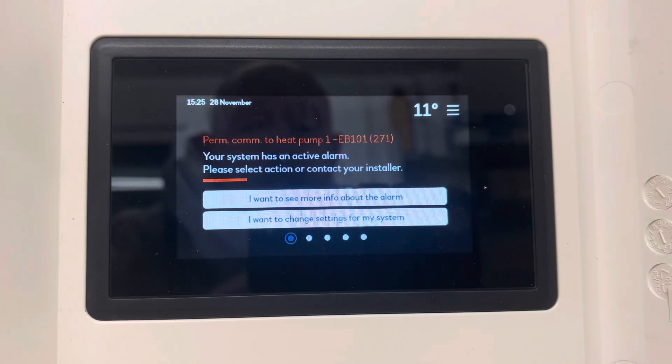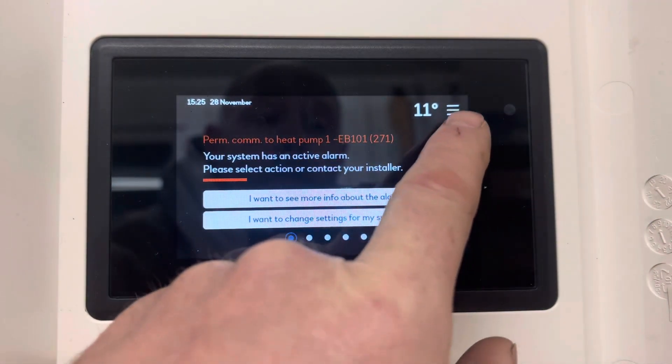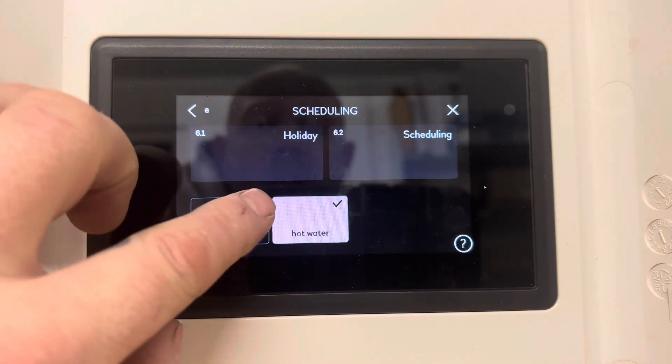We're going to have a look at setting holiday schedules now on our NIBE SMO S40 control. Ignore this error here — this is just a dummy control. So we need to press the button in the top right hand corner. We'll go down to scheduling, then add new mode.